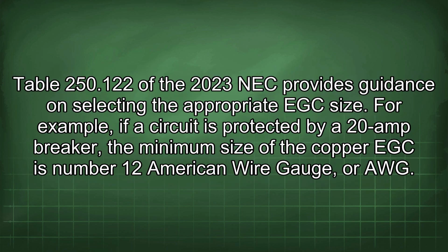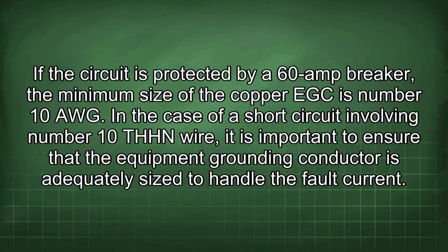Another important consideration is the size of the equipment grounding conductor. The NEC specifies the minimum size of the EGC based on the size of the overcurrent protective device protecting the circuit. Table 250.122 of the 2023 NEC provides guidance on selecting the appropriate EGC size. For example, if a circuit is protected by a 20 amp breaker, the minimum size of the copper EGC is number 12 American wire gauge, or AWG. If the circuit is protected by a 60 amp breaker, the minimum size of the copper EGC is number 10 AWG.